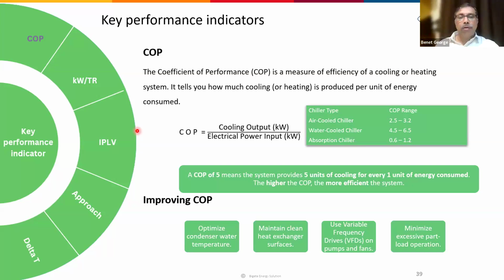The reason is all the air conditioning systems are typically designed for the peak condition in the summer. You know that this will happen once in a while. So a chiller or an air conditioner will work at 100% load typically 1% of the time, and it will operate at a very low load maybe 10% of the time. So that is why this IPLV value is there.